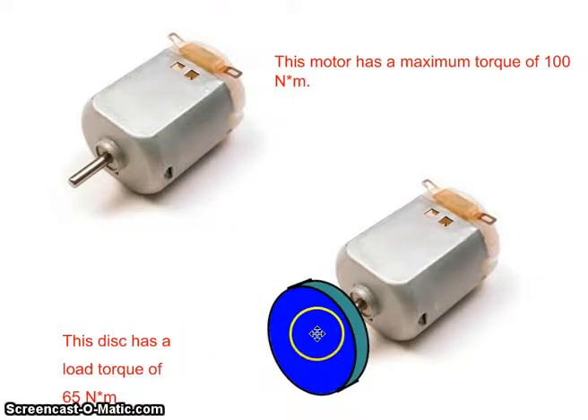This is our merry-go-round, if you will. There are formulas based on shape, size, mass, and so forth, so we can figure out what the load torque is. Let's say we knew that the load torque of this disc was 65 Newton meters. Well, this 100 Newton meter motor would be sufficient for the task.